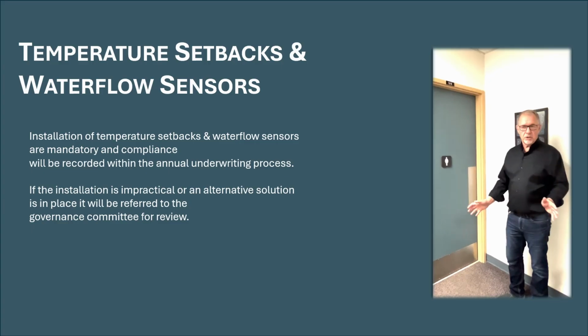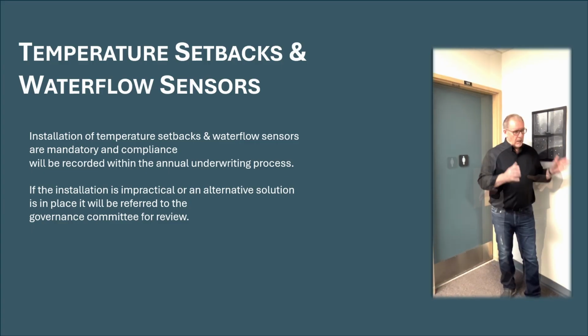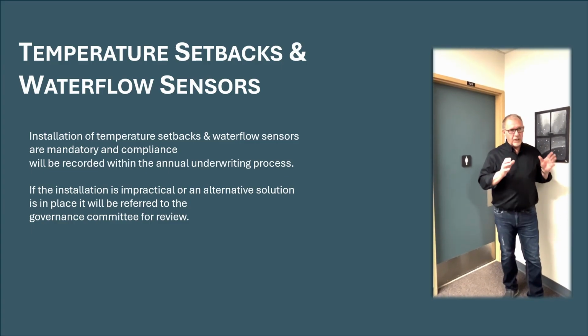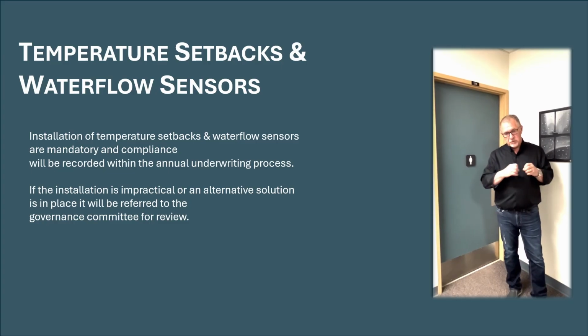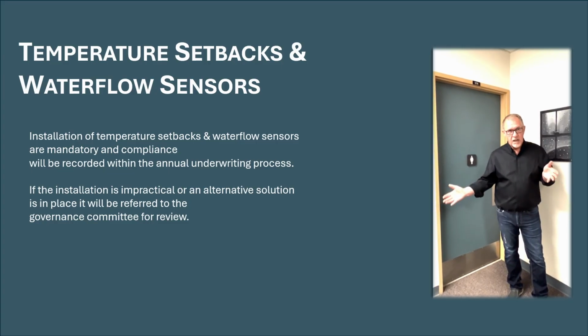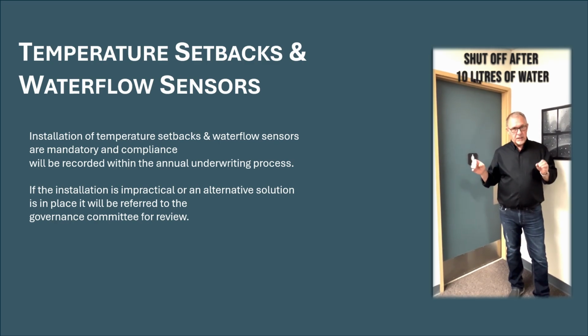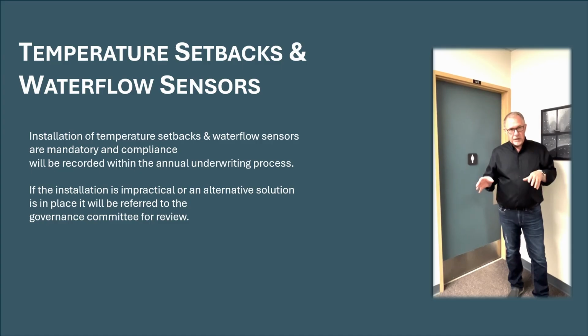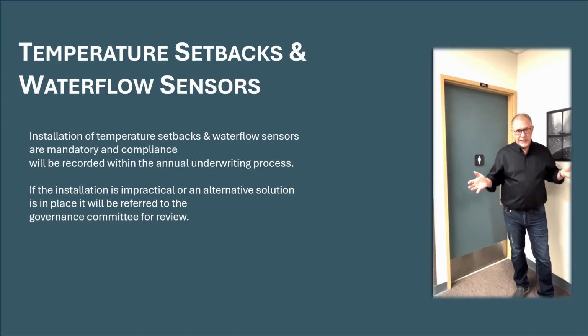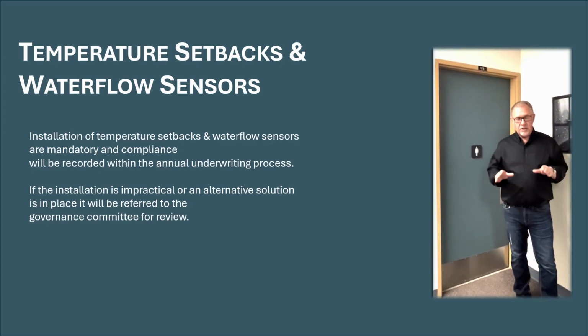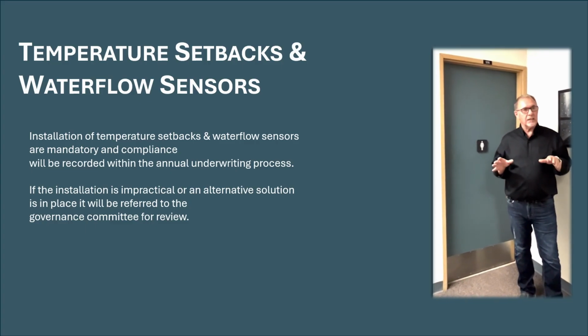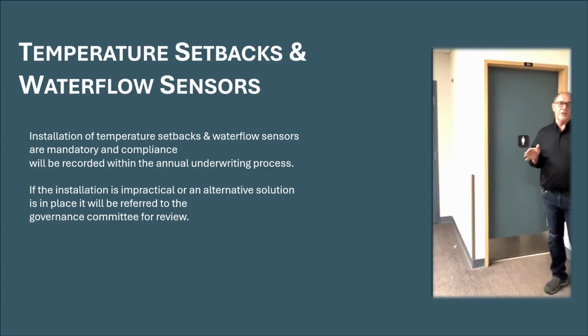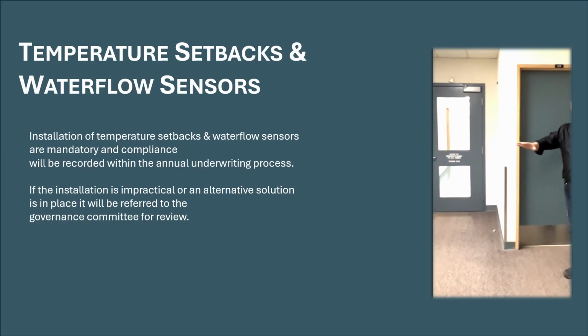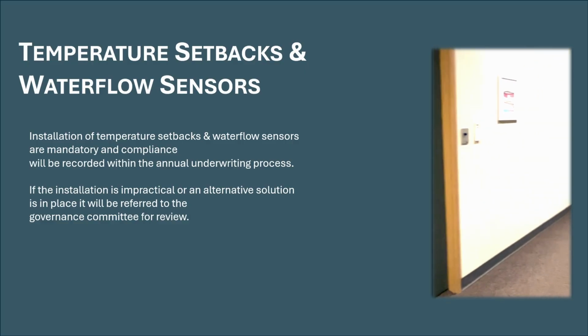So a few years ago, we did have a water leak. The toilet bowl emptied, but then the flush valve within the toilet bowl triggered, and it was trying to fill a bowl that wasn't there. And our system shut that off after about 10 liters of water had spilled on the floor. What it boiled down to for repairs was about a few hours of caretaking work to clean up the mess. That had happened when no one was around. It could have led to hundreds of thousands of dollars of damage by flooding our entire office area here.